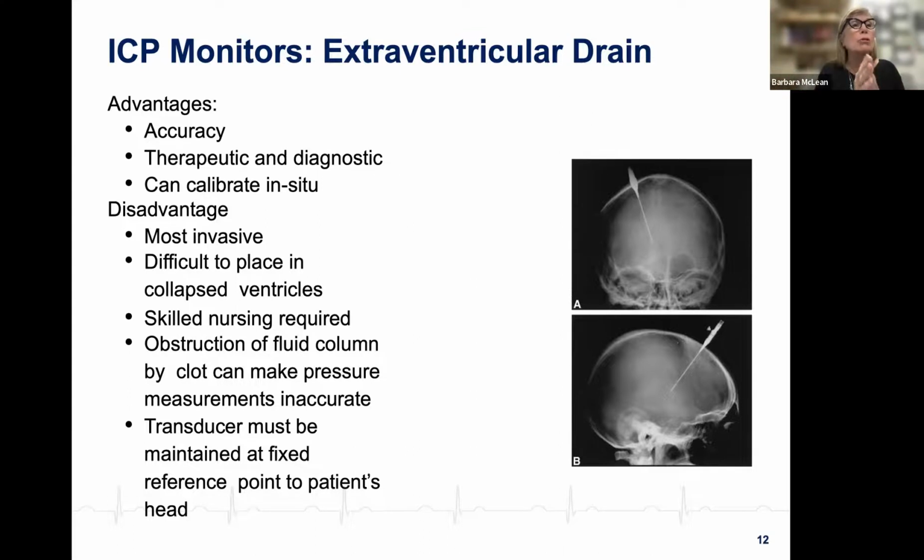At the transducer, once you have flushed the pressure tubing, you have a deadhead on the end of the transducer that would normally be connected to fluid-filled tubing. Now, you still have a zero reference at your transducer, and you still have a connection to the patient, right? So that's really, really important.